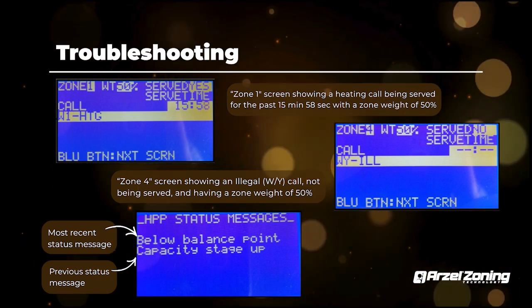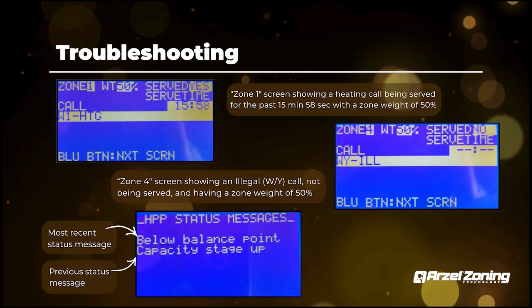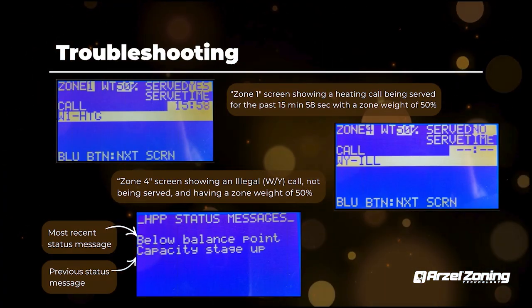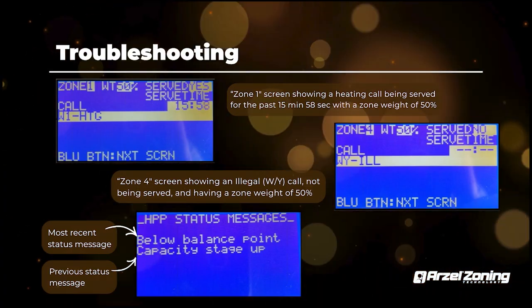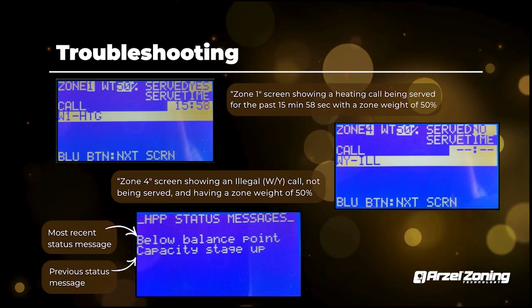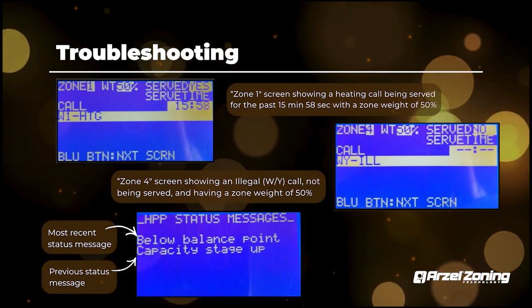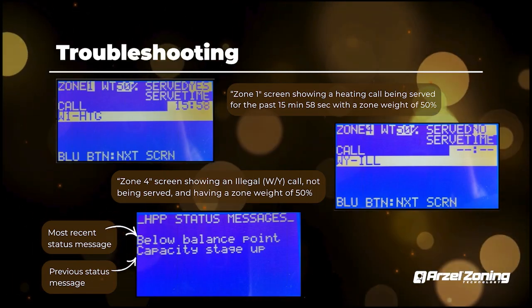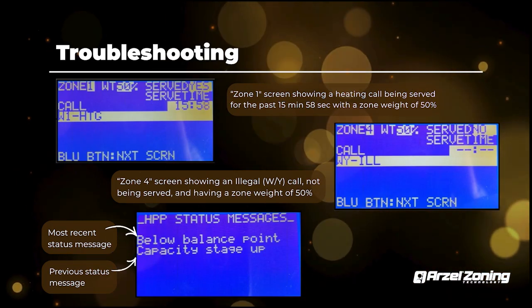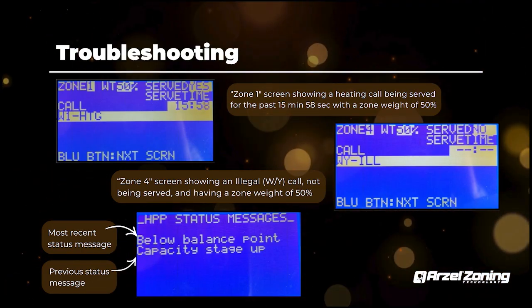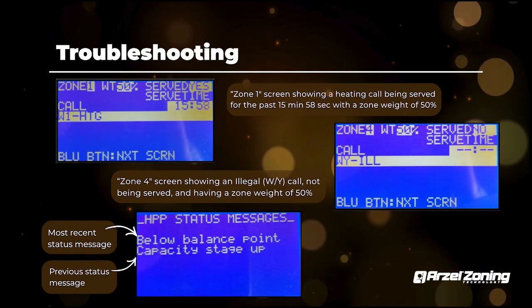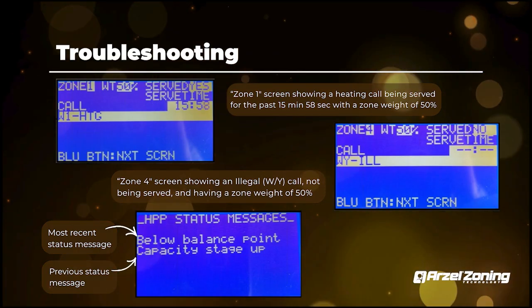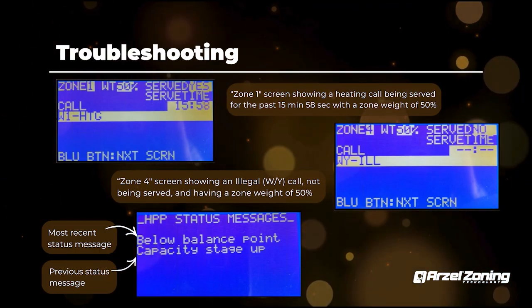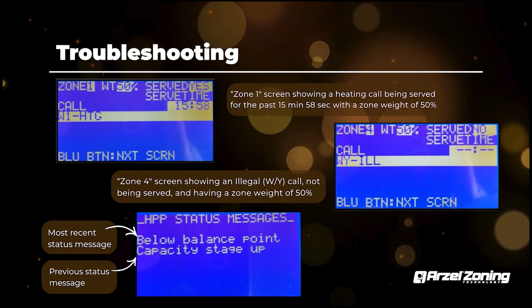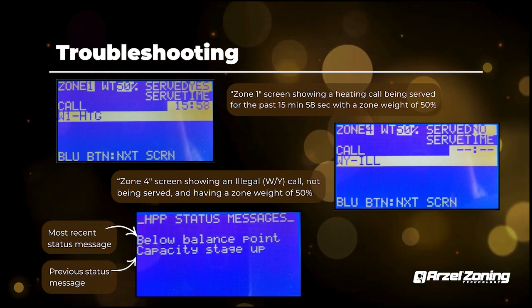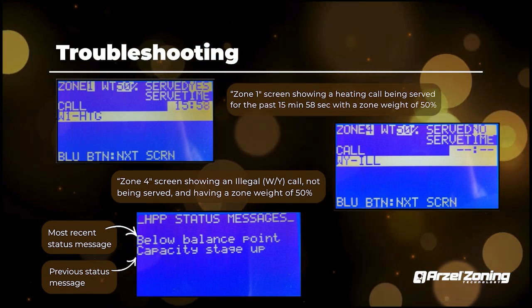WY-ILL. So this is one of the calls we get the most of in tech support with the HeatPumPro: I got a call on whatever zone and it's not working. And then we get them to go through the screens, we get to this and you see something similar, like a WY-ILL. Anytime you see that, it's an illegal call on the panel. The panel's not going to serve that call. In this case, it's because you're energizing heating and cooling at the same time. Just remember with the HeatPumPro, all your other zones besides zone 1 need to be heat, cool only thermostats.